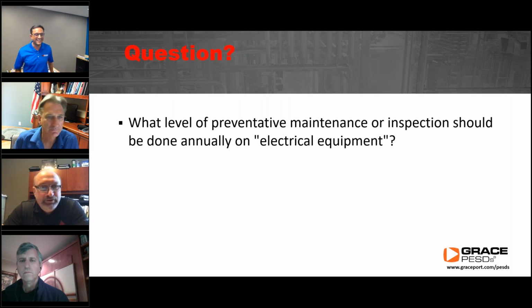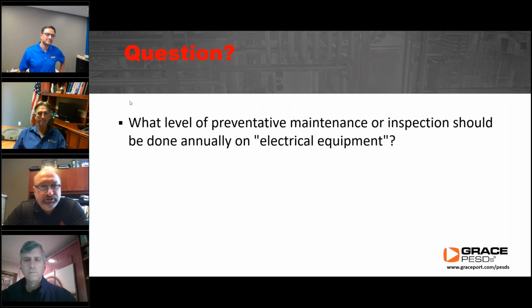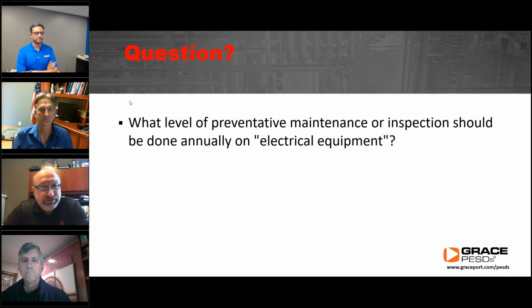In Z462, we took a different approach. We focused on safety, so maintenance for safety. We have these protective devices we're relying on, and if they don't operate at all, or operate slower than predicted, the incident energy will go up. That's a difference between Z463 and 70B.